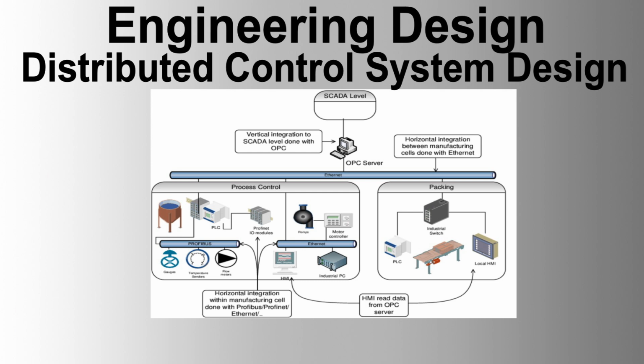Software requirement 1. DCS software and displays. The VDU graphic displays must be consistent with existing ones regarding colors, symbols, keystrokes, and methods of access. The DCS must maximize the use of standard proven software, minimizing custom programming. An established method for controlling and validating software development and subsequent modification must be available. All software and associated hardware necessary for programming and modifying system software must be included. Detailed configuration and custom display, building documentation, and technical assistance during configuration activities must be provided. All software must be developed using provided typical functional block diagrams and P&IDs.